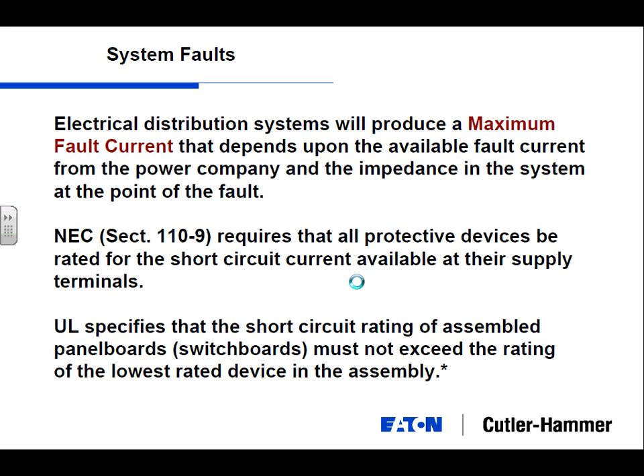Just thinking about it, the higher the fault current, the more rugged we have to make the distribution equipment. The more rugged we make the distribution equipment, the more it's going to cost and the more we're going to charge you. And that funnels all the way back to the owner. NEC requires that all protective devices be rated for the short circuit current available at the supply terminals. So your first switchboard as your service entrance, maybe 65,000 amps, will have to be labeled and rated for 65,000 amps. By the time you get into this point in here, it will be much lower.